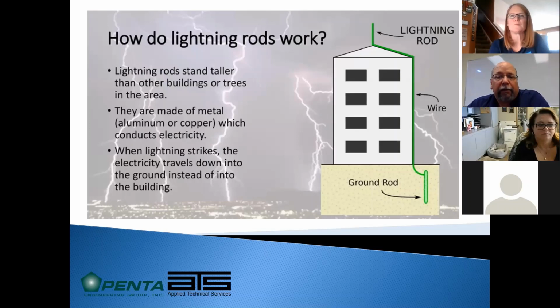Basically, when they are installed on top of the building, we want them to extend a certain height above anything that we're protecting. We're going to create a zone of protection with lightning rods. Every component of the system is made of aluminum or copper, and it conducts the electricity to the ground using what we call a down conductor, which is just a long cable that's connected to either a ground ring or a ground rod. So again, we're providing that preferred pathway, making sure that energy goes straight to the ground and not into the building.